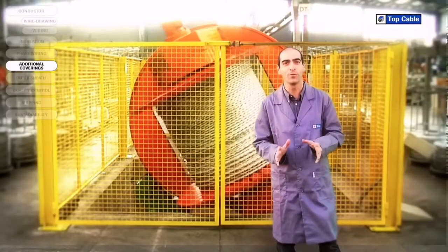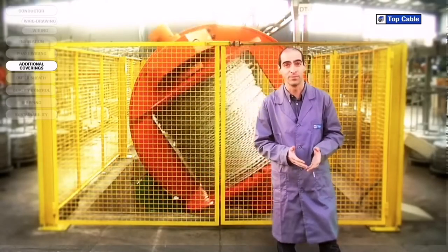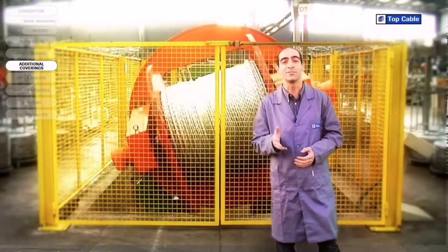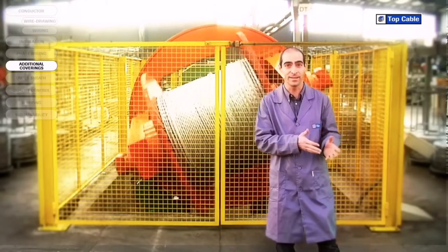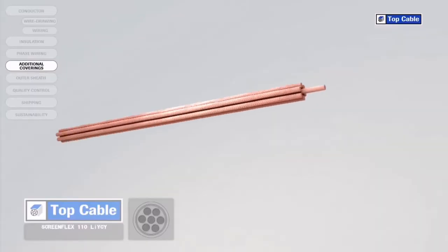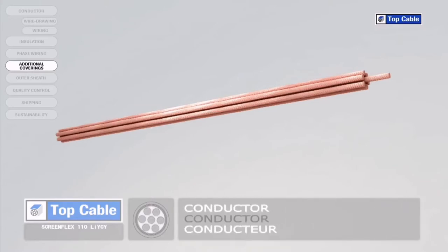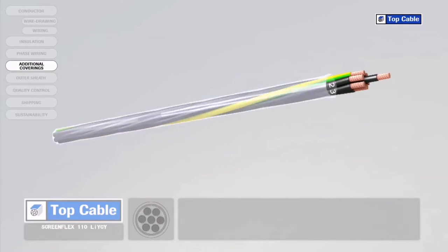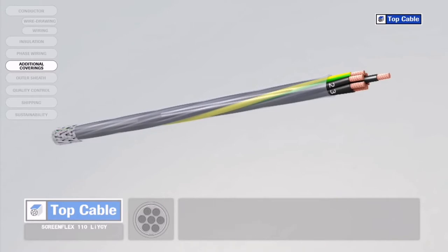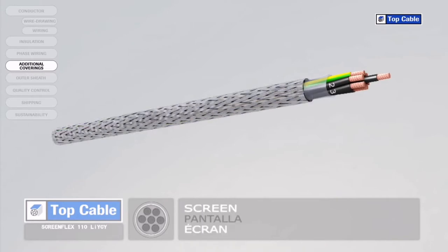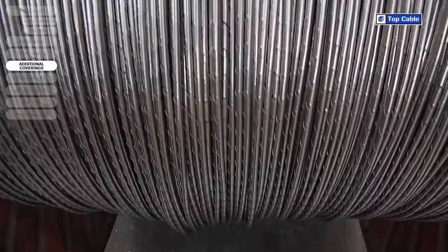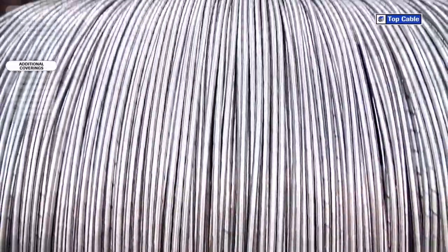In some cases the cable may require additional elements in order to improve its protection or operation. Electrical coverings, also called screens, insulate the signals that circulate in the cable from possible external interference. They also shield the power cables to prevent them from interfering with adjacent signal circuits. Mechanical coverings, also called armor, protect the cable from external damage that may occur from knocks, rodents, and any other potential causes of damage.